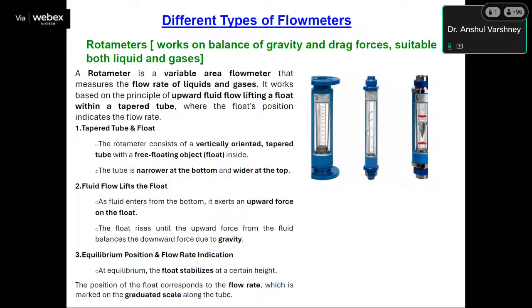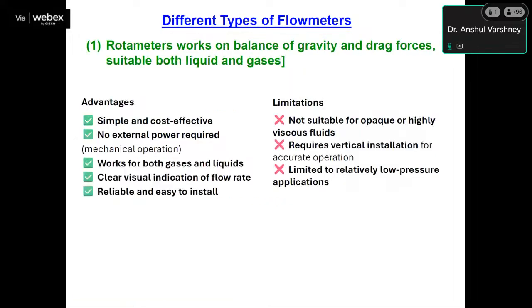The rotameter consists of a vertically oriented tapered tube with a free floating float. The tube is narrower at the bottom and wider at the top. As fluid enters from the bottom, it exerts an upward force on the float, and the float rises until the upward force from the liquid balances the downward force due to gravity. At equilibrium, the float stabilizes at a certain height, the position of the float corresponds to the flow rate, and basically this type of flow meter provides you the instantaneous flow rate.